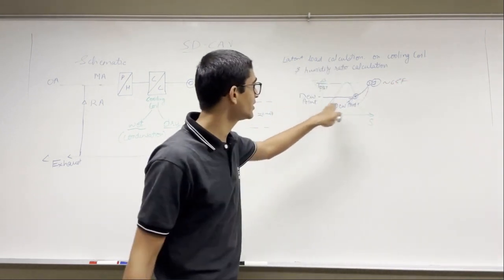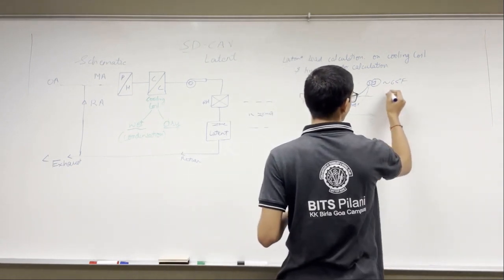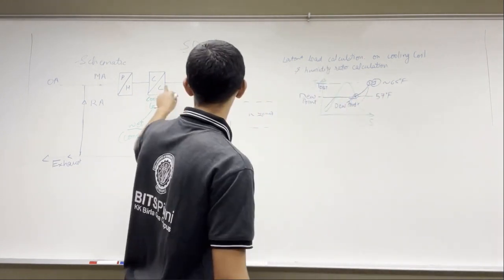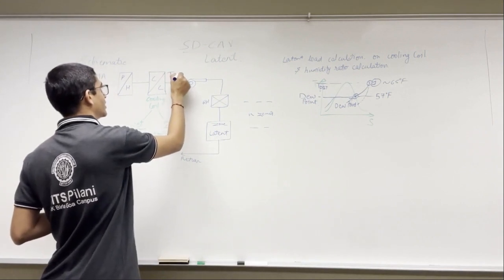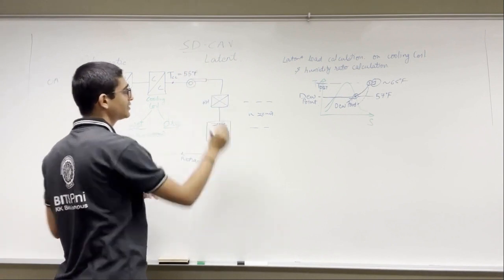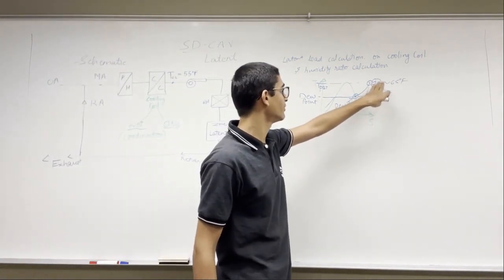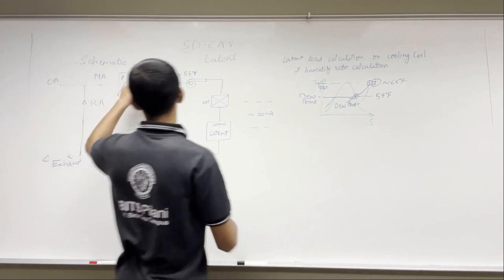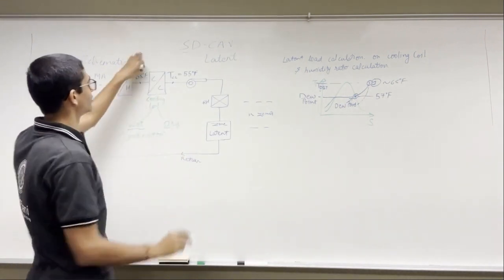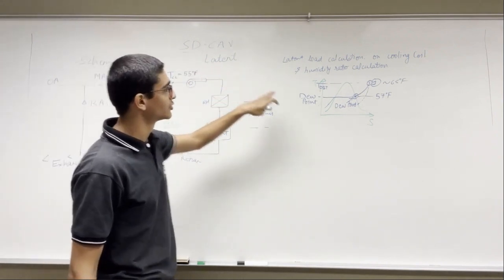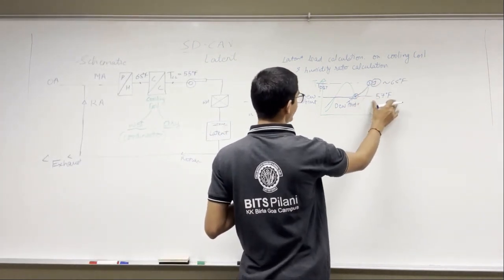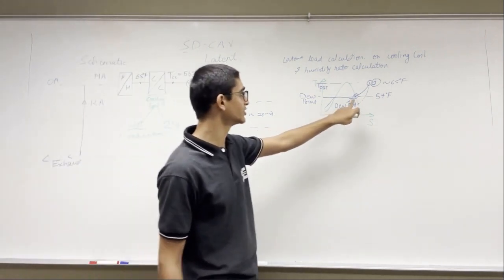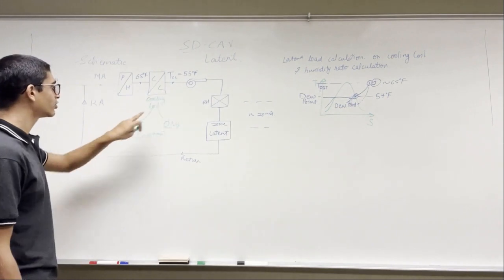The given air coming to the cooling coil might have a temperature of 70 or 65 degrees Fahrenheit. Let's say the dew point temperature for this location is 57 degrees Fahrenheit and our cooling coil leaving temperature TCL is 55 degrees Fahrenheit. The air and water vapor will both be converted to 55 from 65 degrees Fahrenheit — it is cooled to 55, which is below the dew point temperature. Hence the water vapor part will start condensing, and my cooling coil will be wet.